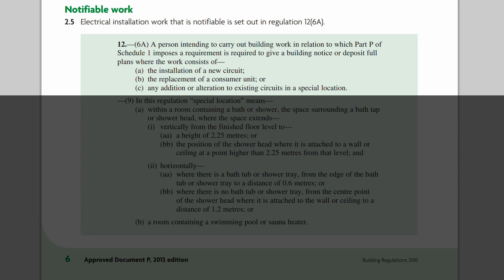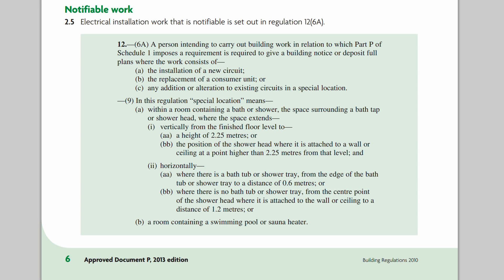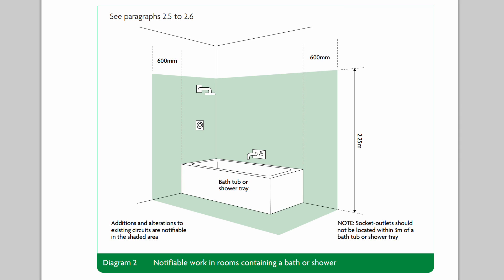Although Part P applies to all electrical installation work, there are a small number of items which need to be notified to the building control authority. The notifiable items are: A — the installation of a new circuit; B — the replacement of a consumer unit; and any addition or alteration to existing circuits in a special location. A special location is defined as a room containing a bath or shower, and the area surrounding the bath or shower within defined distances, as well as swimming pools and sauna heaters.